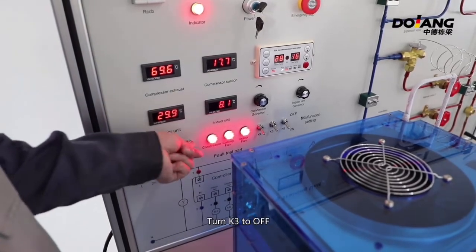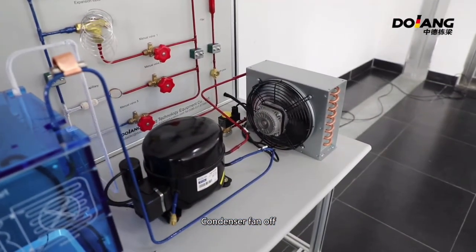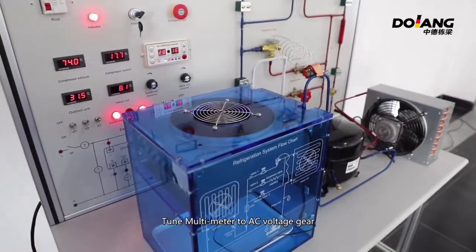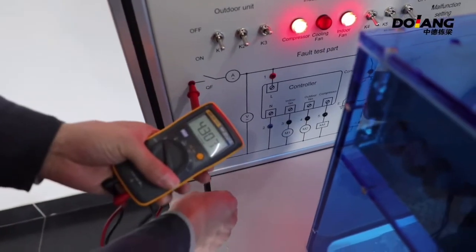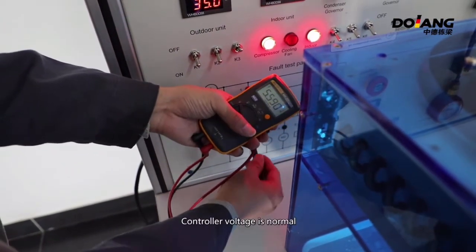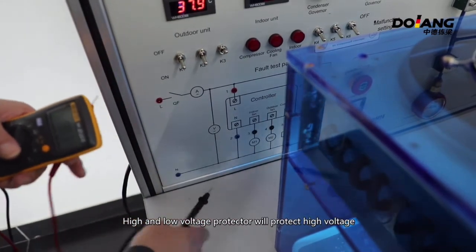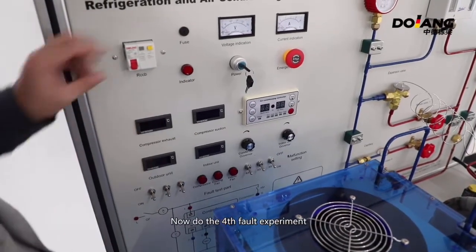Now do the third fault experiment. Turn K3 to off — the condenser fan turns off. Use a multimeter to measure, turning it to AC voltage gear. The voltage is normal at one point and the controller voltage is also normal. If the fault experiment continues for a longer time, the high and low voltage protector will trip due to high voltage. Press the reset button on the high and low voltage protector to reset.